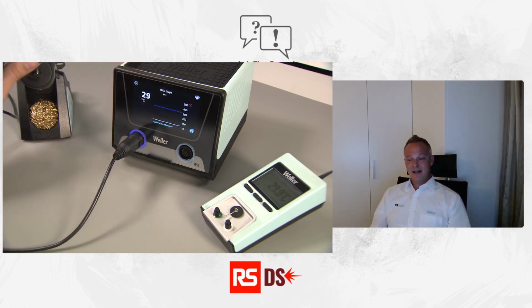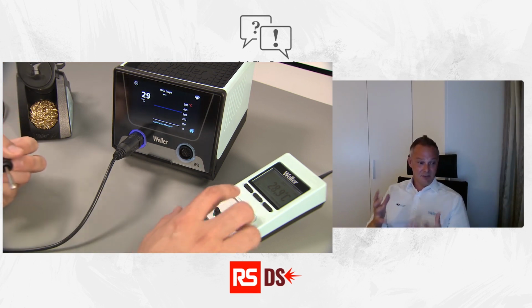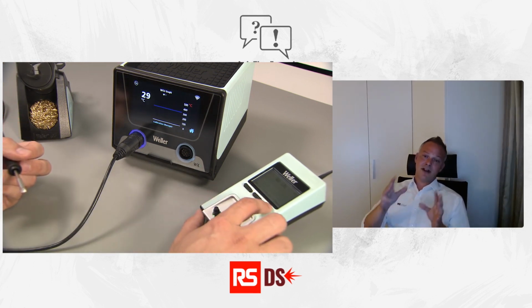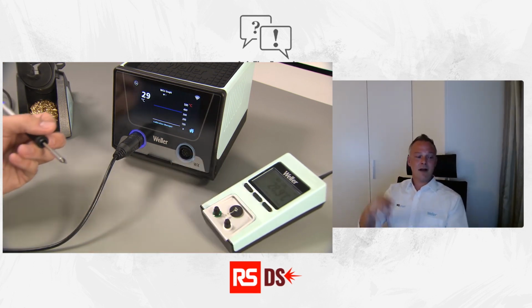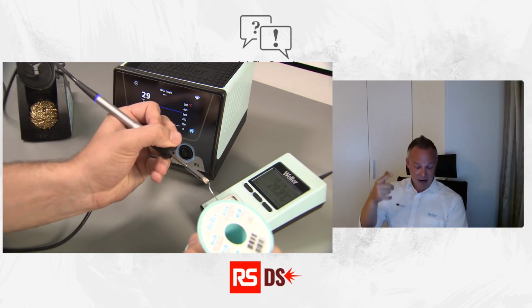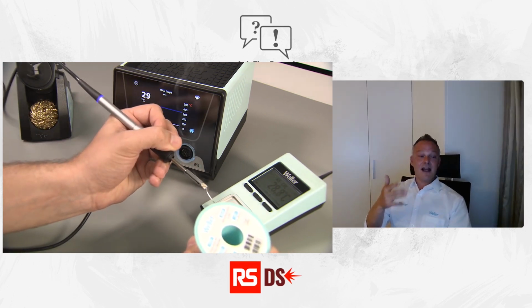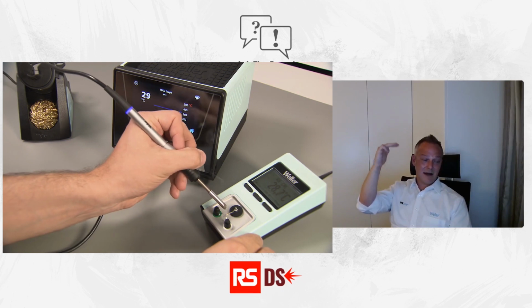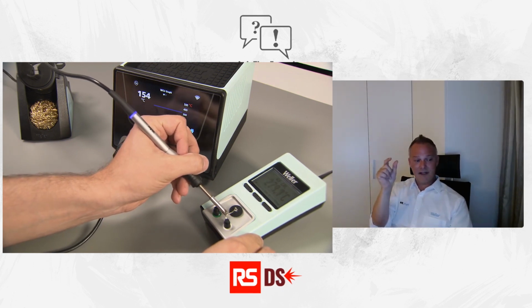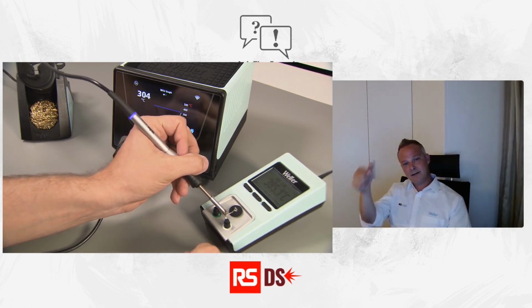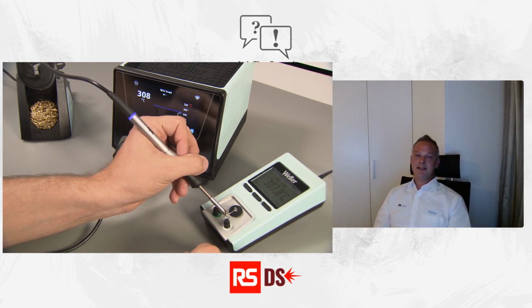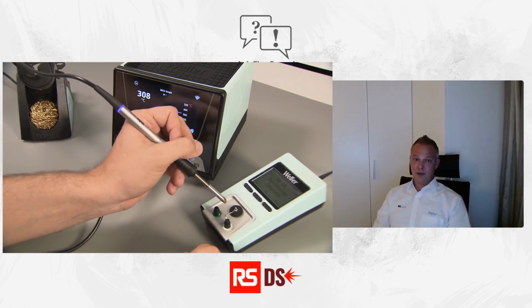But the combination is smart - if the WCU is connected to a WXsmart unit and you are measuring a smart tool and tip, the calibration elevates to a smart auto calibration, because the offset value will be automatically addressed to the smart tip itself. This is, again, the highest level of calibration you could achieve today.